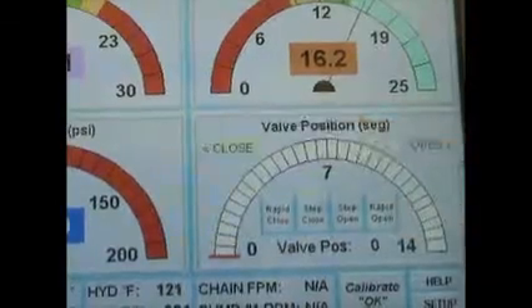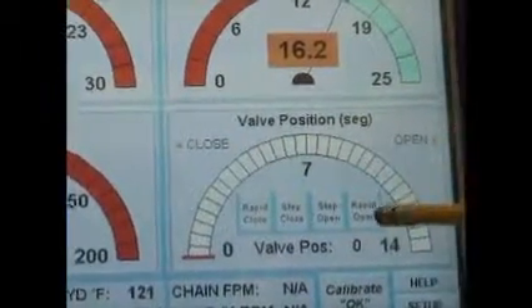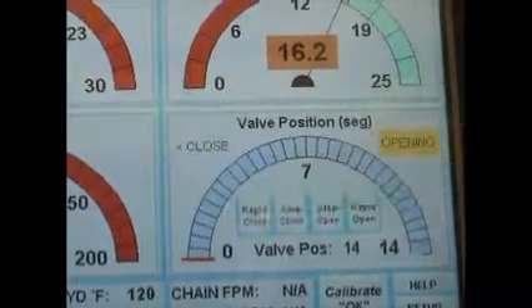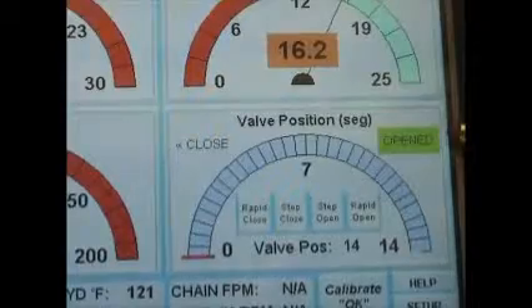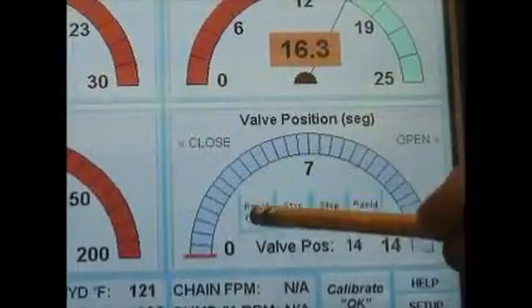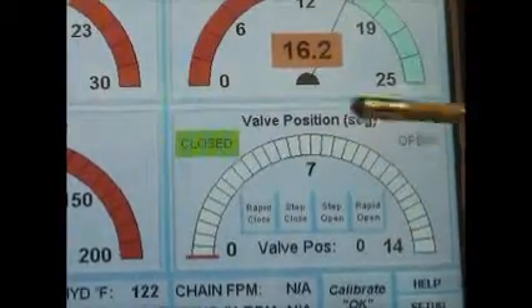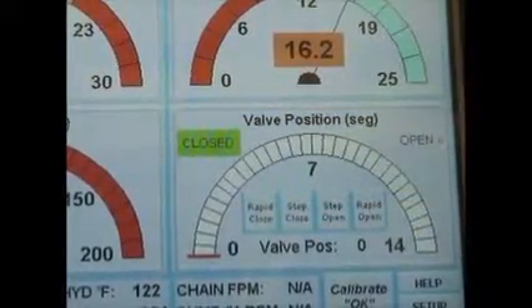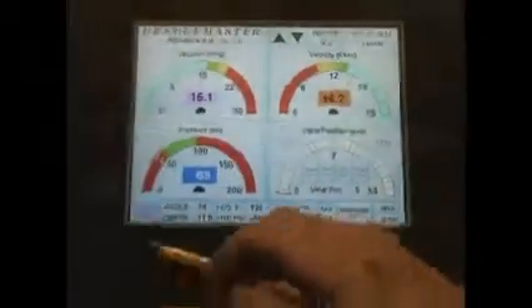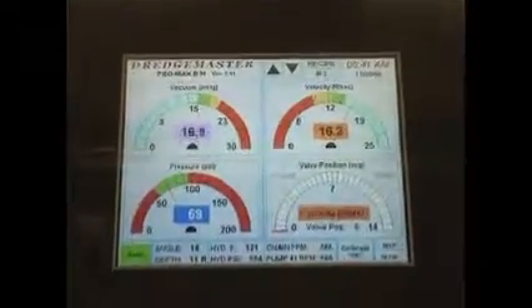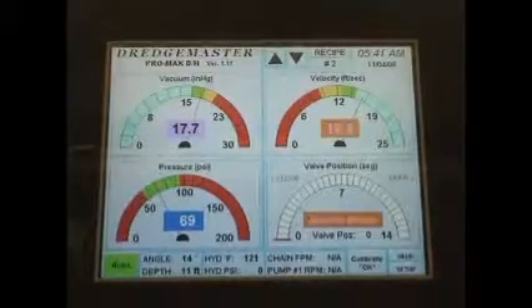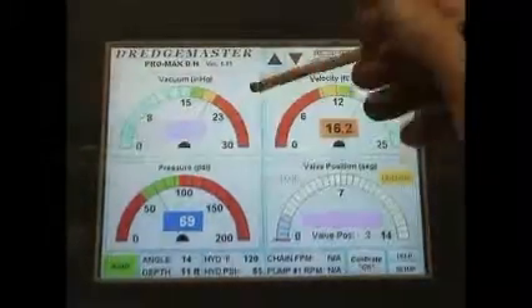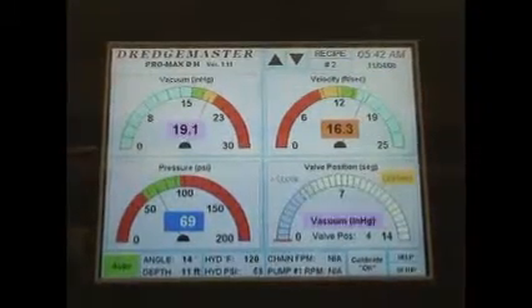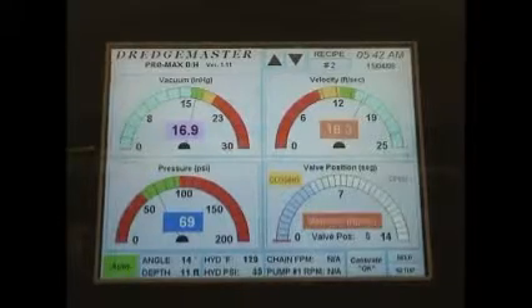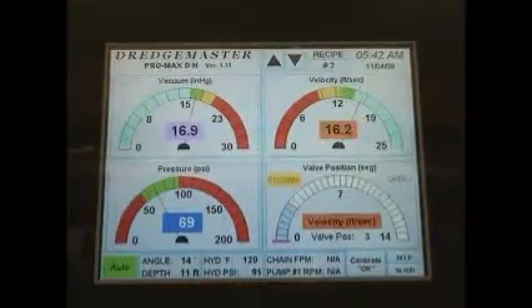If we want to rapidly fully extend the valve open all the way, we can hit the rapid open button. We have now just fully extended the valve all the way. And if we want to rapidly close the valve, we touch the rapid close button, and now we have totally closed the valve. If we want to go back to automatic mode again, we simply touch this manual button to auto, and now the valve is in automatic mode. If we increase our vacuum up there on the vacuum gauge, we can see that we're in the yellow zone. It is now triggered automatically based on your color zones. 99% of the time your operator will be running in the automatic mode.